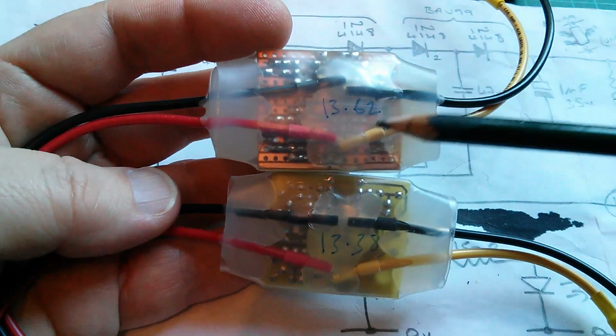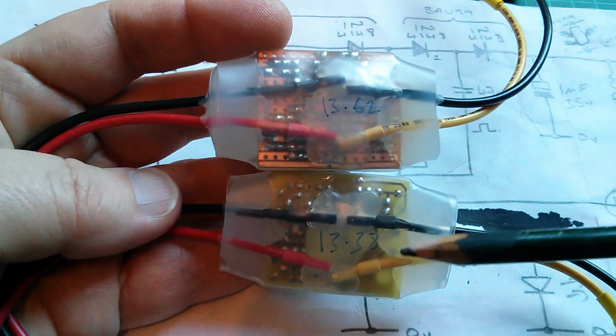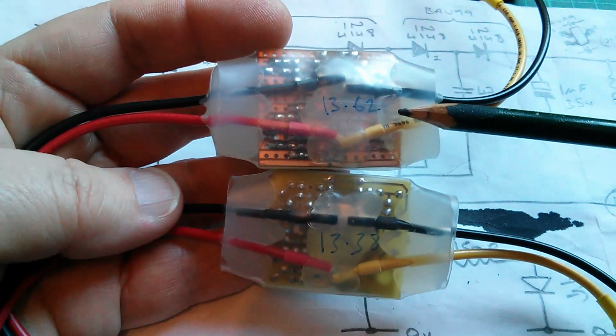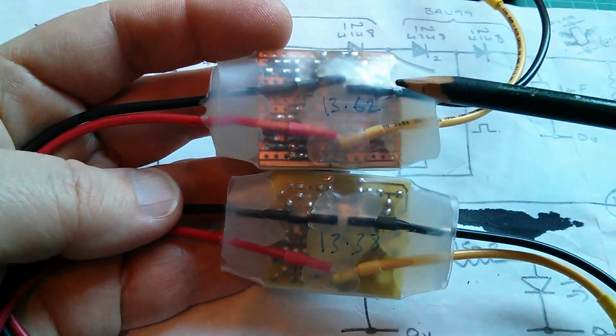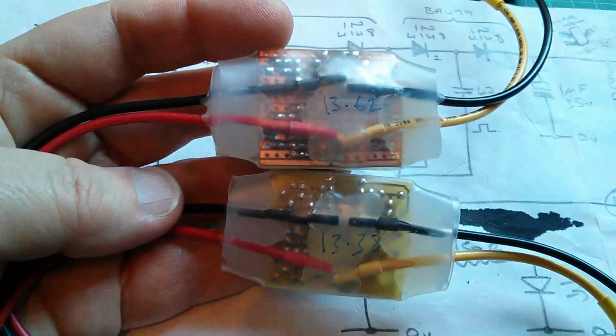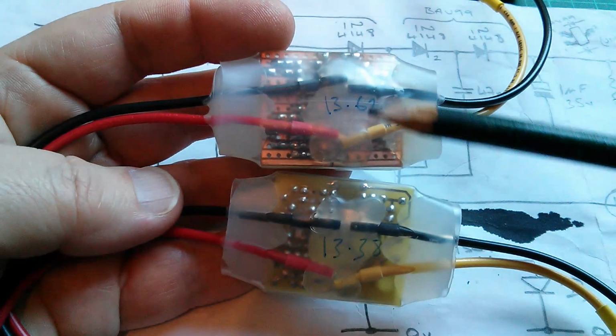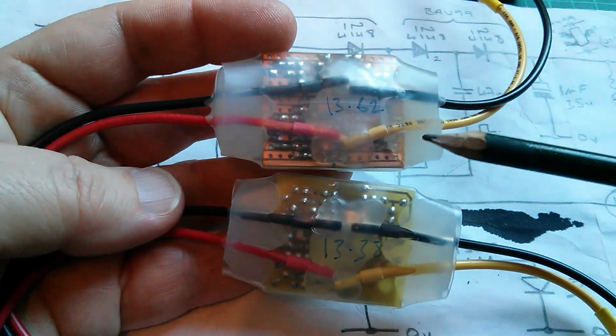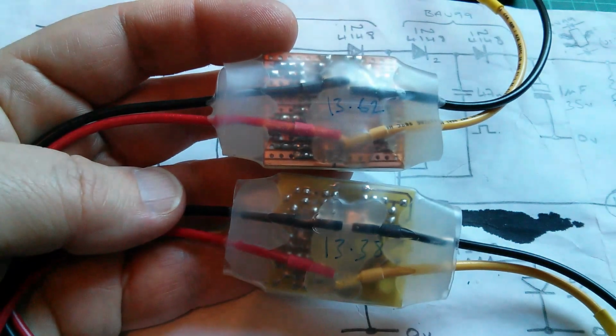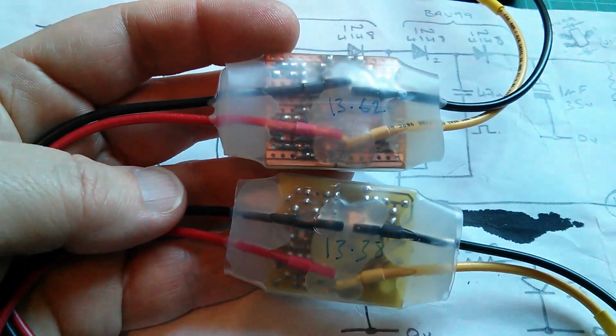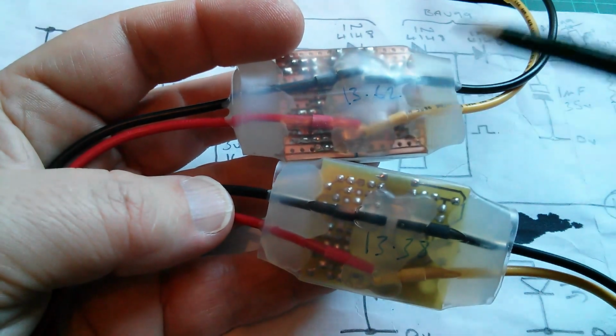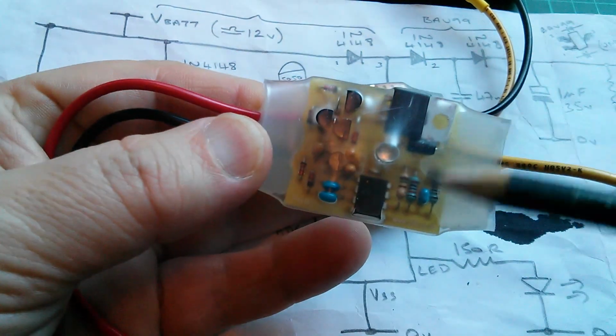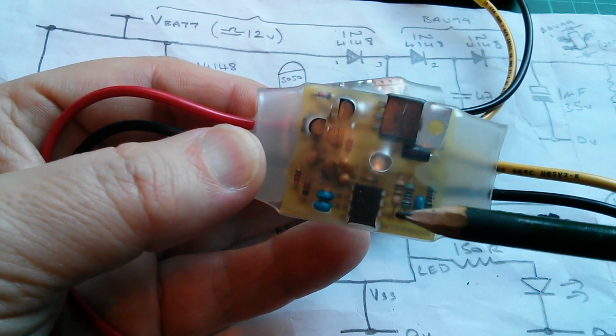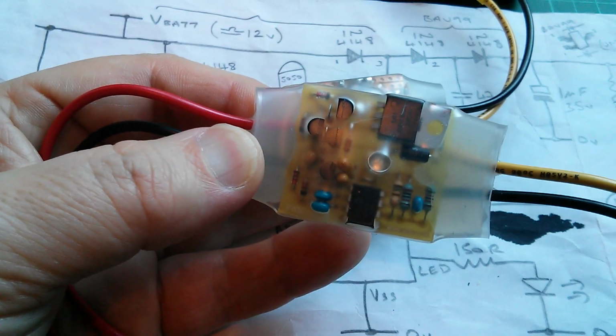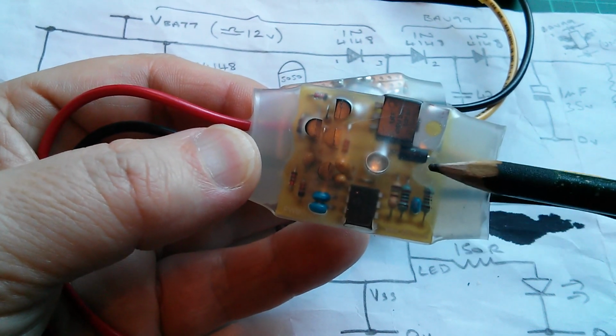So the point is, this error in the unit's nominal accuracy can be compensated for. There can be a procedure put into the test setup that can take this error out, and this problem can be completely eliminated. I never got round to doing it while I was manufacturing these things, but it is something I'd like to do now that this unit is going open source for people who want to build this for themselves. Now the E2PROM in this unit is currently used for holding a bit which determines whether or not this thing has the LED enabled or disabled, but because that caused all sorts of problems with people not understanding how it worked, I'm getting rid of that feature.